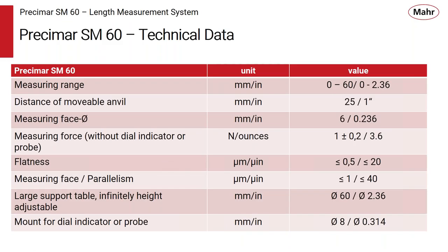Just a little bit of the nuts and bolts here about the technical data. We said we have a measuring range of 60 millimeters or 2.36 inches, but really the distance of the movable anvil or the sensitive anvil is 25 millimeters or 1 inch. So you can put a 1 inch indicator in the product and have a direct reading measuring instrument. Or if you want, you can use a short range high precision probe and have a short range comparative system. 6 millimeter diameter on the contact faces. We have some reference flatness specs and parallelism specs, which are in line with precision length measuring systems. We have a support table, and the mount for the indicator or the probe is 8 millimeters.